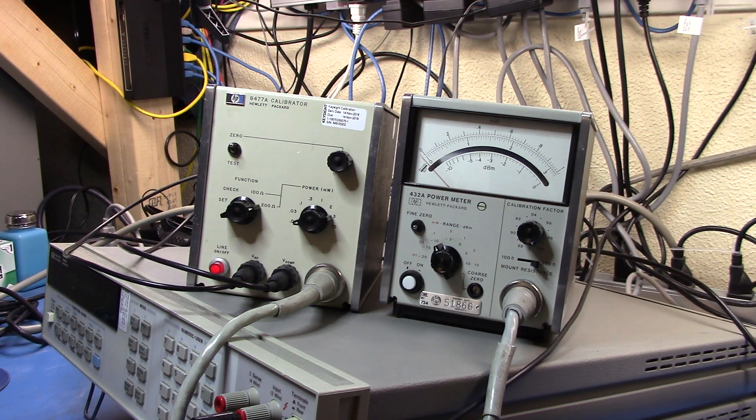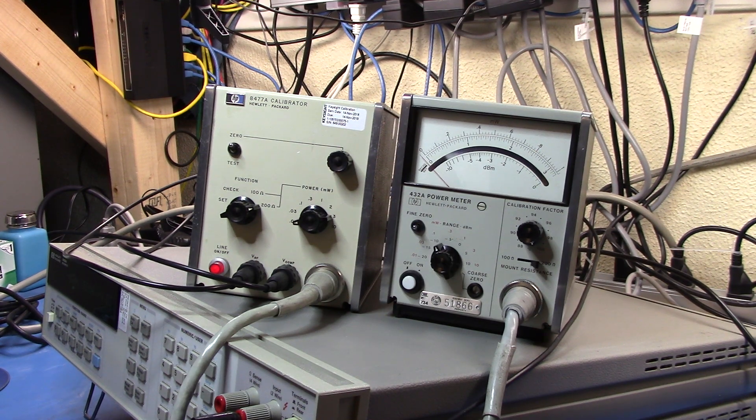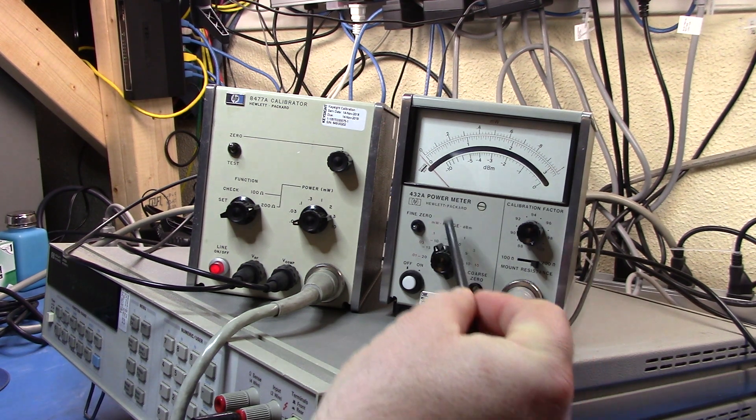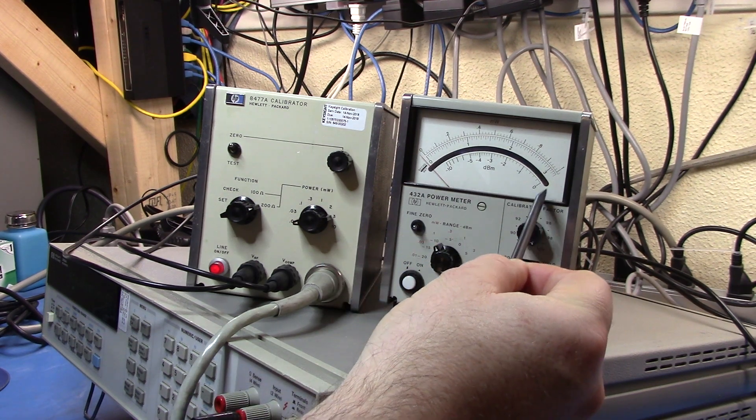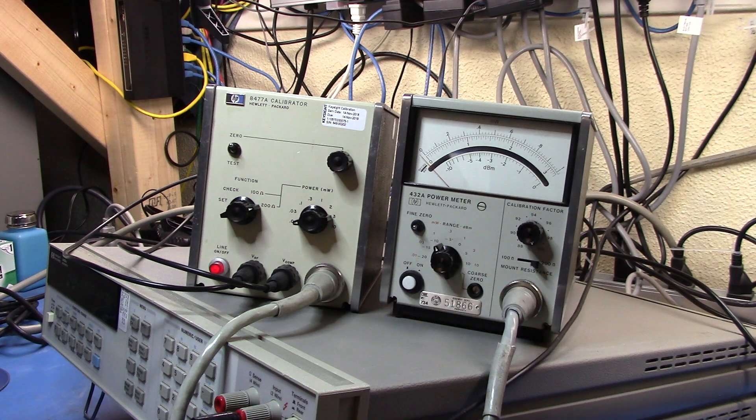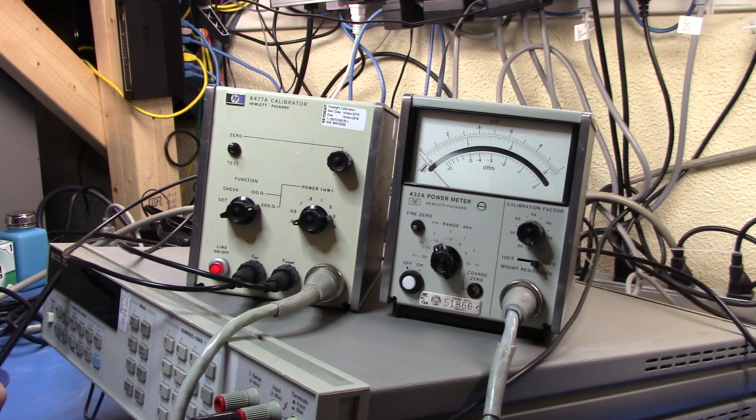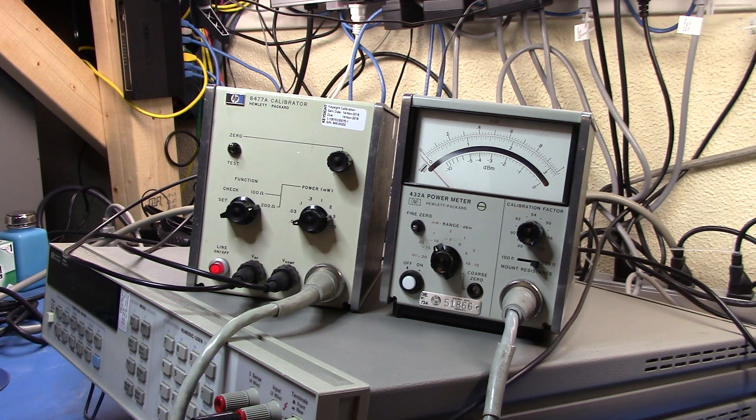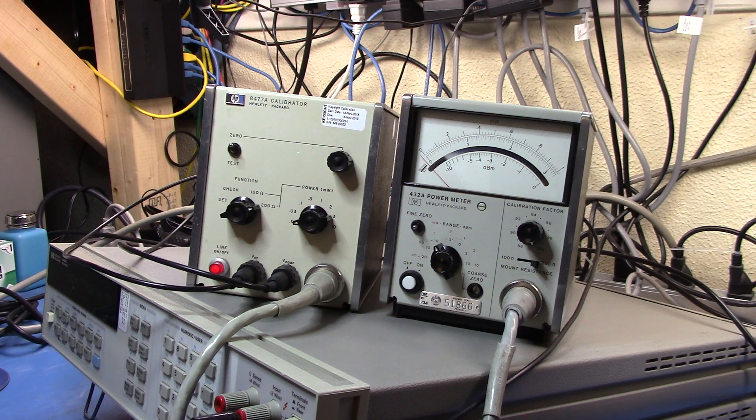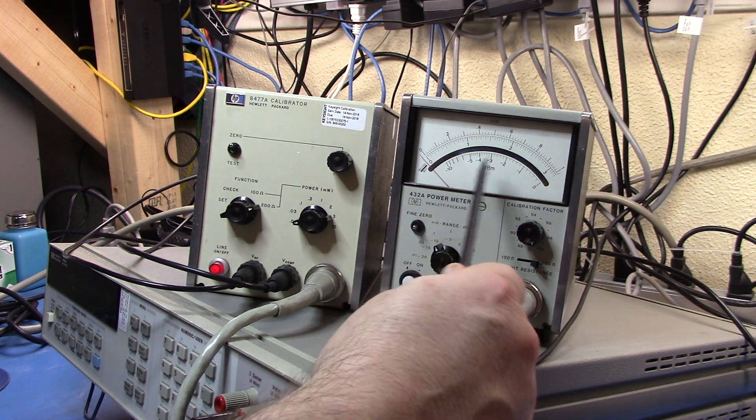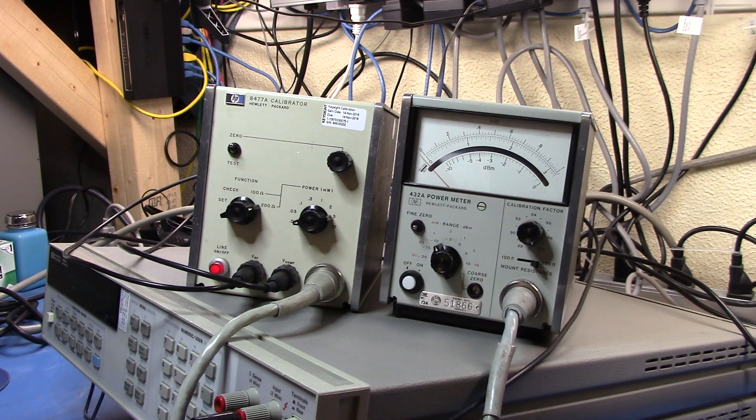The first thing we want to do is a meter accuracy test. This is going to check where the meter needle is in terms of the actual scale here and tell me what the output is. I have the 3458A here connected up so that it's reading the recorder information that's coming out of the back of the 432A. That recorder information is 0 to 1 volt depending upon where in the meter scale the needle is.